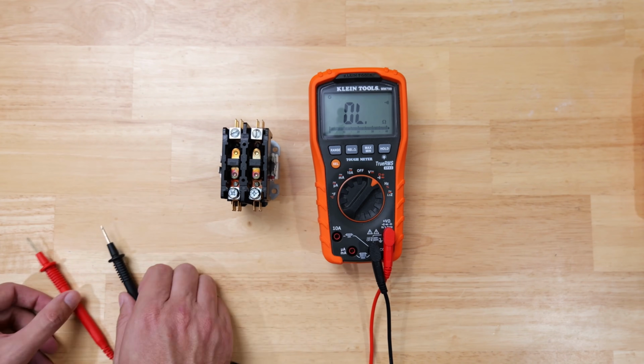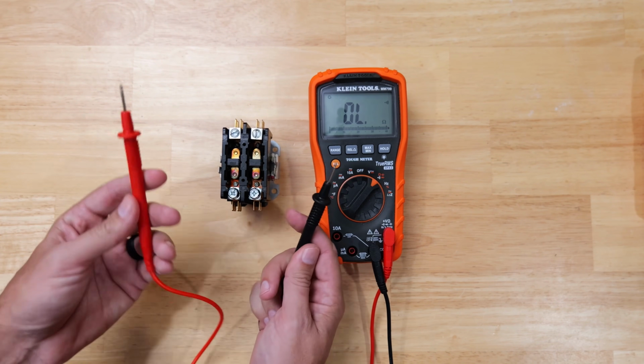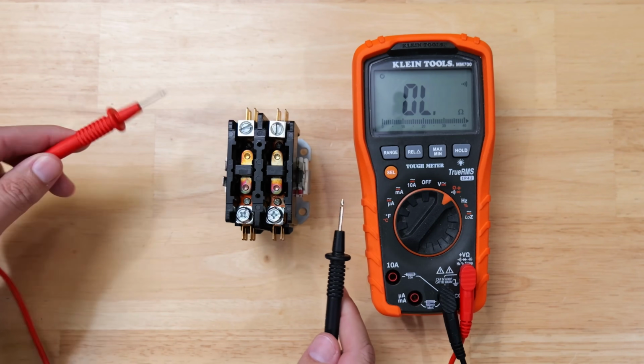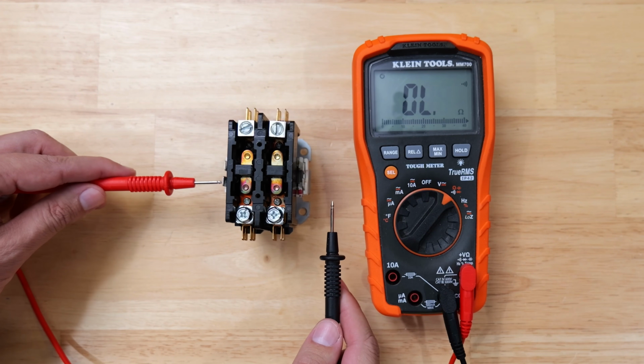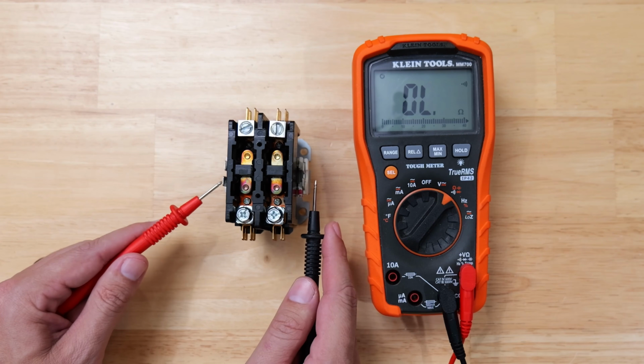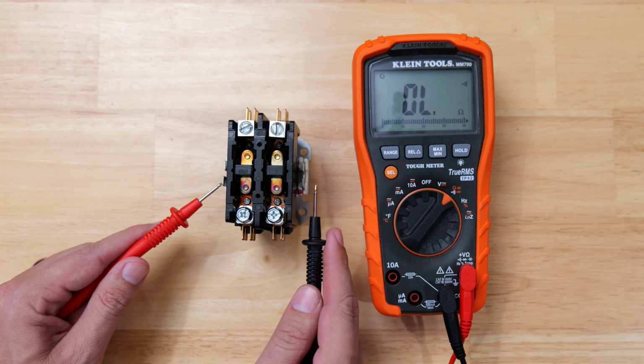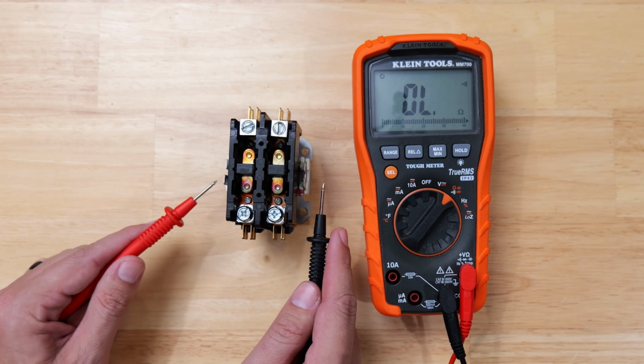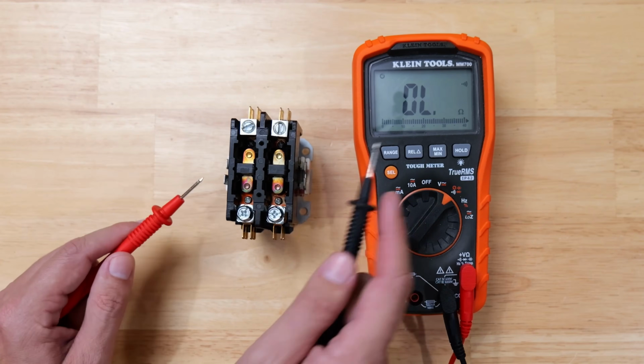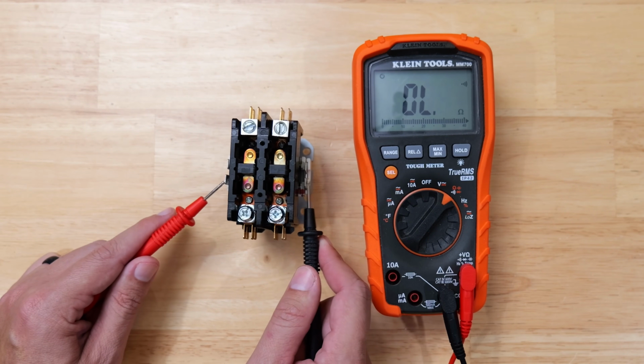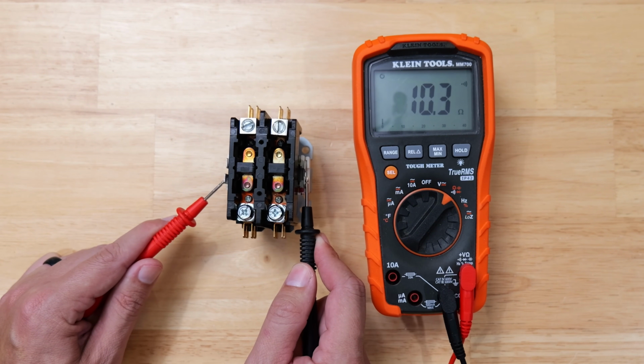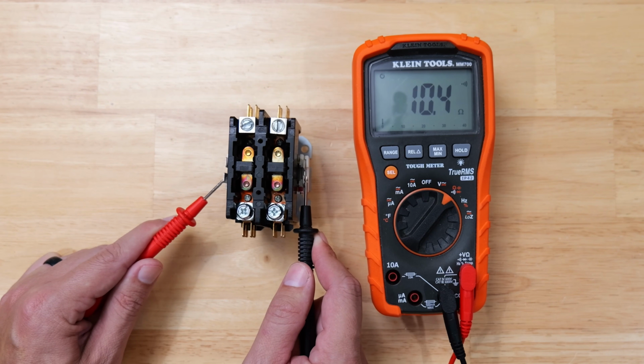I've got it on that setting, so all I need to do is take my probes, put one on the left side terminal, and the other on the terminal on the other side. We should also get an audible continuity reading along with the resistance display. So I'll go ahead and test it. There's that sound telling us we have continuity, so we know there's a connection, and we're reading out at 10.4 ohms.